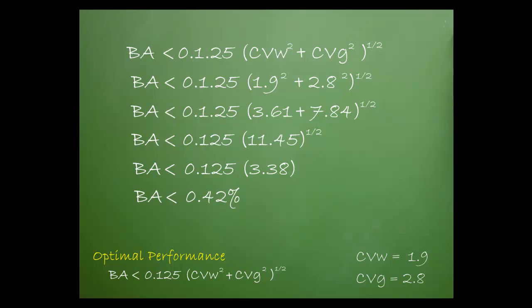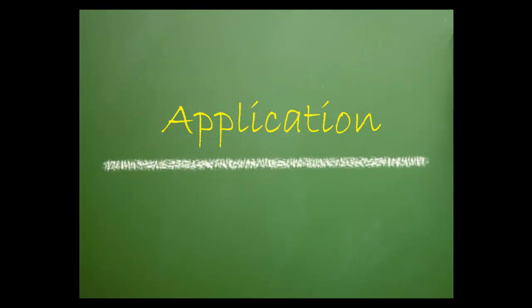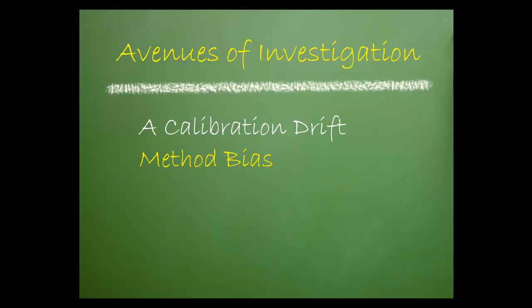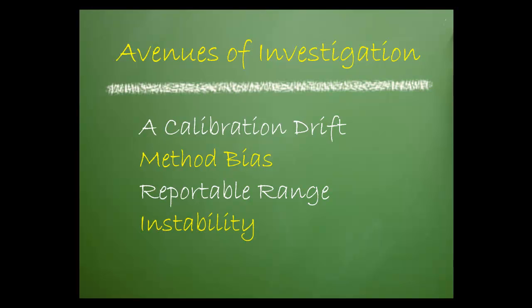Now that you've established an SEA, let's talk about practical application. If you experience results that fall outside of your bias goal, here are some possible avenues of investigation. Be on the lookout for calibration drift. Look for method bias — this is bias attributed to unsatisfactory laboratory performance. Also consider reportable range error or a miscalculated mean. Instability errors are related to materials, instrument performance, instrument components, or proper maintenance.